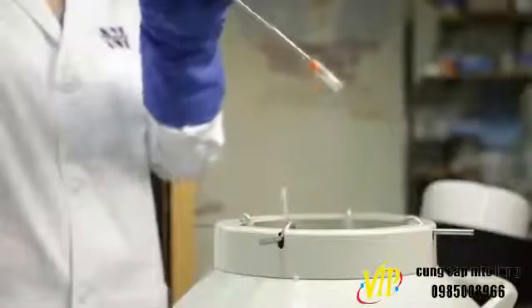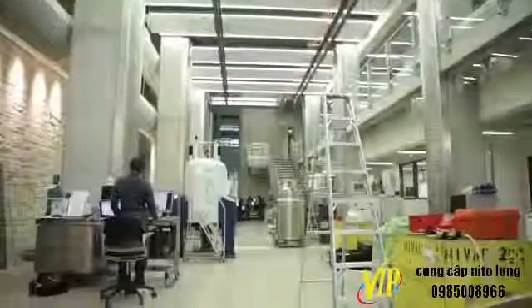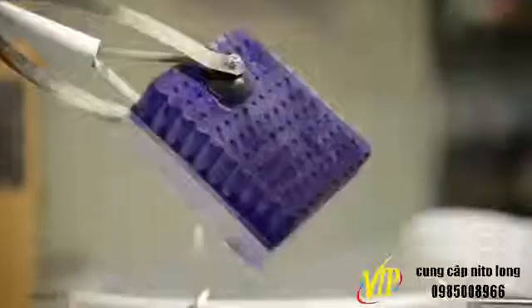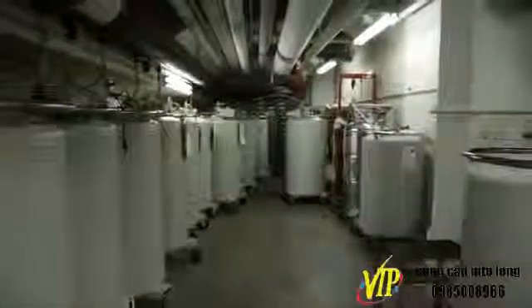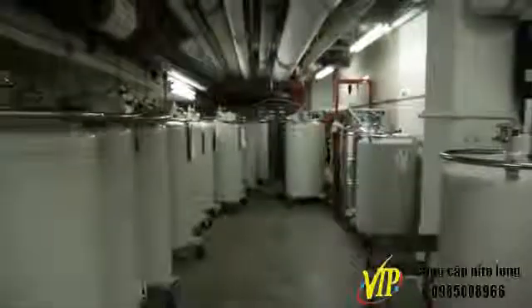Pipes, vessels, NMR tubes, and cryotubes with trapped liquid can violently rupture, causing injury and exposure. Avoid storing liquid nitrogen tanks near heat sources, with direct exposure to the sun, or in locations where the temperature can fluctuate widely.